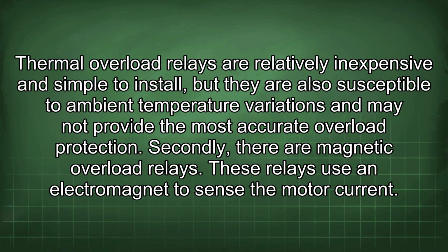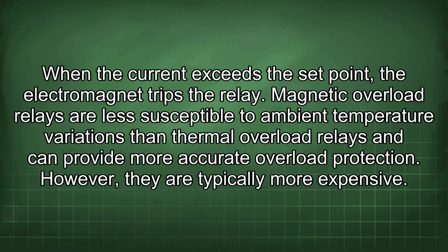Secondly, there are magnetic overload relays. These relays use an electromagnet to sense the motor current. When the current exceeds the set point, the electromagnet trips the relay. Magnetic overload relays are less susceptible to ambient temperature variations than thermal overload relays and can provide more accurate overload protection. However, they are typically more expensive.